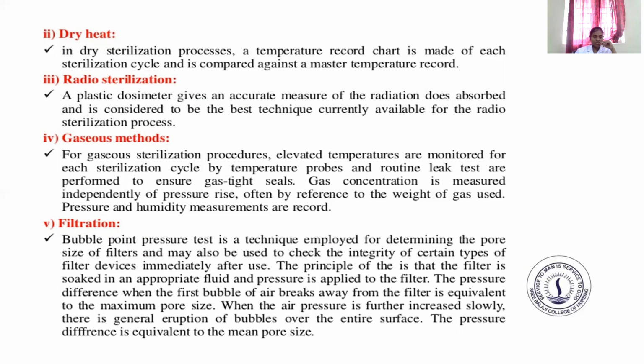And fifth one, filtration. Bubble point pressure test is a technique employed for determining the pore size of filters and may also be used to check the integrity of certain types of filter devices immediately after use. The principle is that a filter is soaked in appropriate fluid and pressure is applied to the filter. The pressure difference when the first bubble of air breaks away from the filter is equivalent to the maximum pore size. When the air pressure is further increased slowly, there is general eruption of bubbles over the entire surface. The pressure difference is equivalent to the mean pore size.